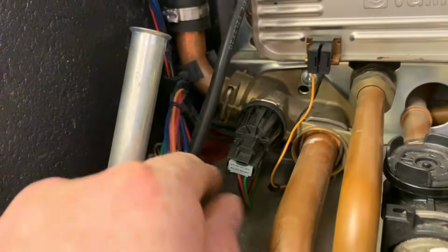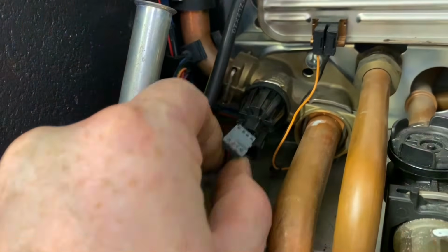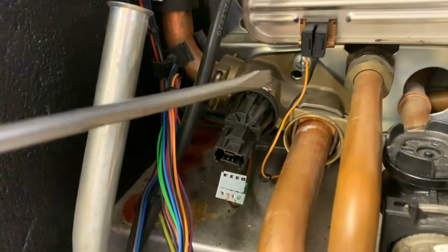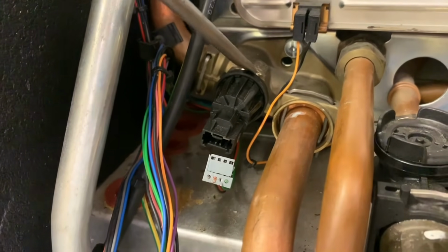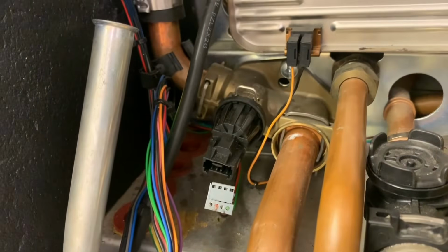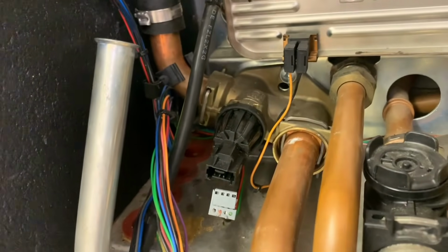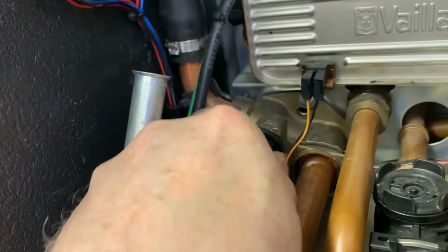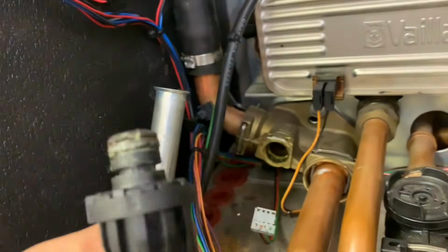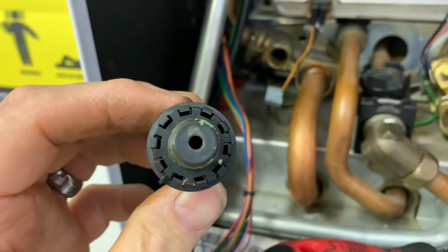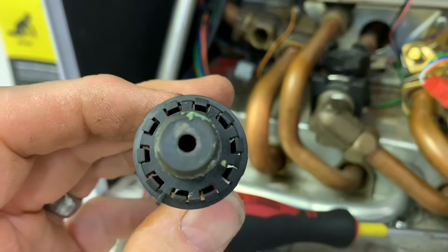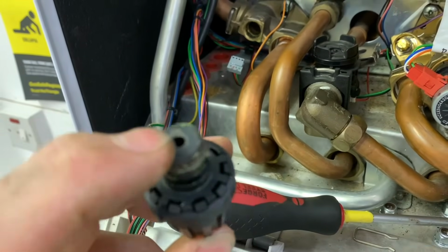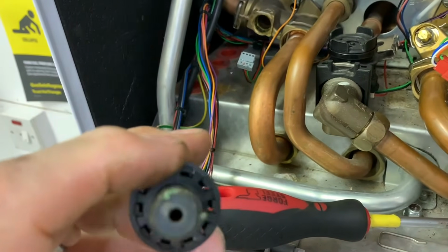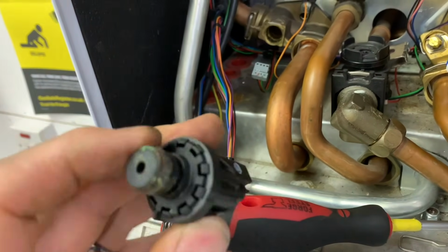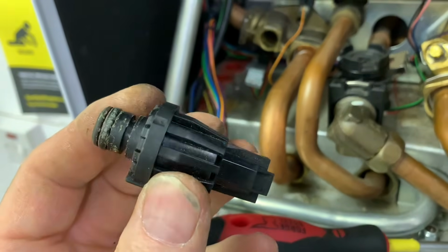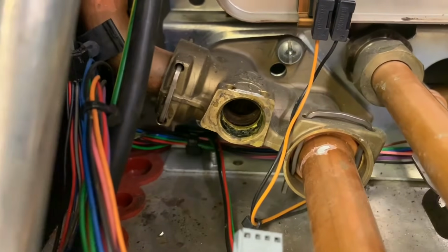So again, dead easy to remove. First of all, let's pull the wire off while we've got the pin still in. And we've got another little pin. My screwdriver might be too big. No, it did it. Pull that pin out, and then the little beggar should come forward. Okay, again with an O-ring. So what happens with these is all the debris goes inside there because there's a little pressure switch inside there. Some guys I've seen bypass them by putting screws in and all sorts, but dead easy to replace. The only problem you get is lots of water coming out there.